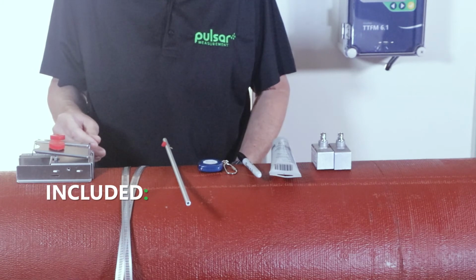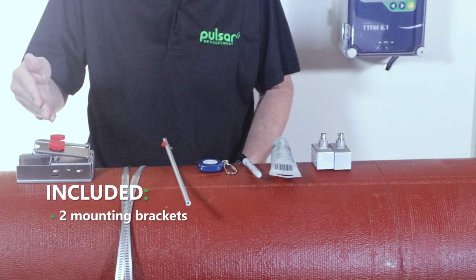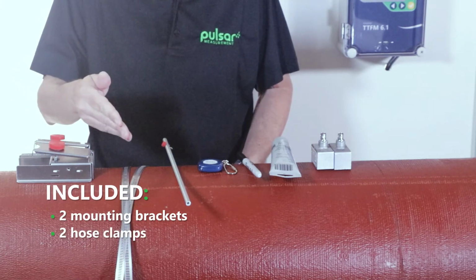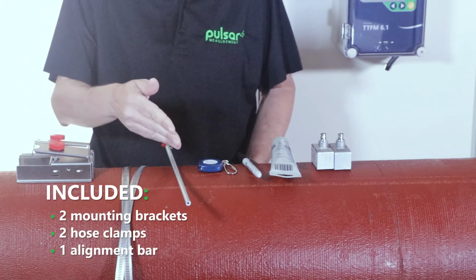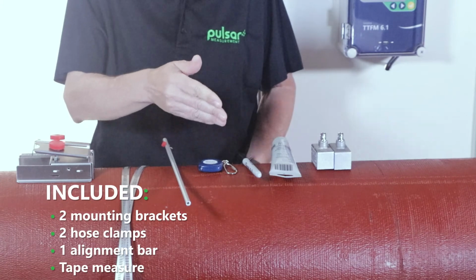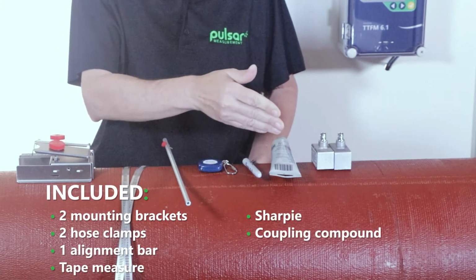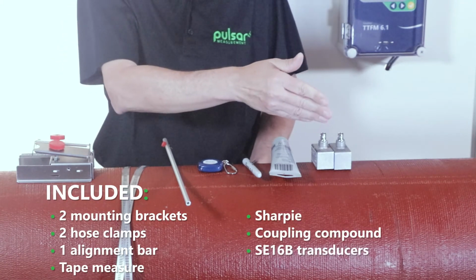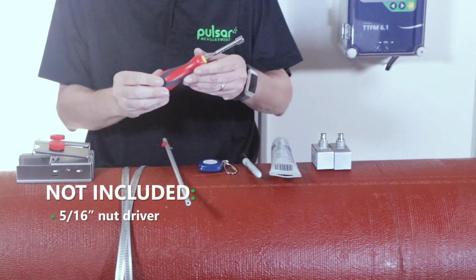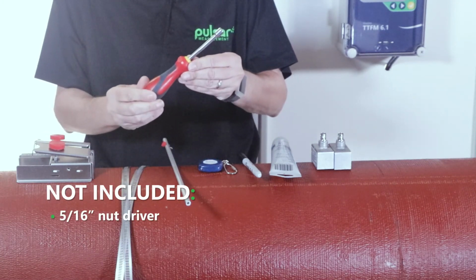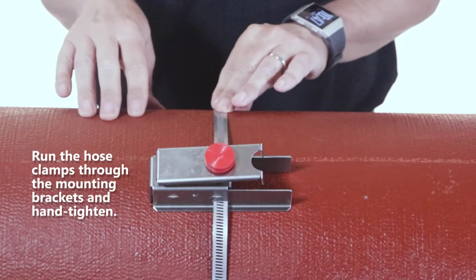To do this, you'll need the following items. They all come with the unit: 2 mounting brackets, 2 hose clamps, an alignment bar, a tape measurer, Sharpie, coupling compound, and the 2 transducers. Additionally, you'll need a 5/16 nut driver. It's time now to begin the installation.